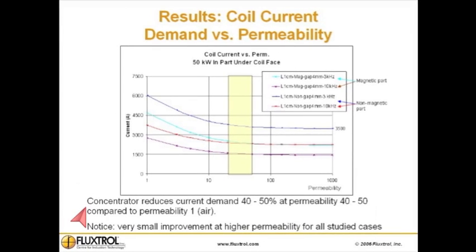Coil current demand versus permeability. A concentrator reduces current demand 40 to 50 percent at permeability 40 to 50, compared to permeability 1 (air). There is a very small improvement at higher permeability for all studied cases.